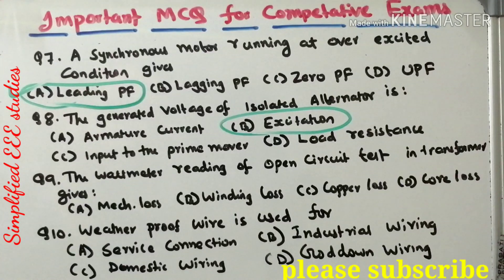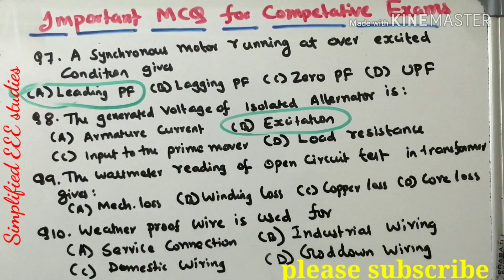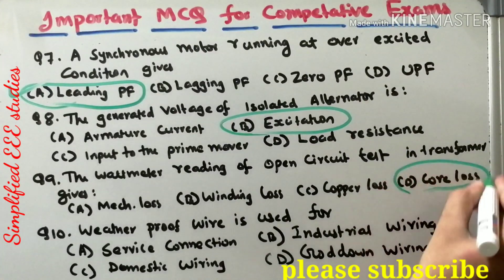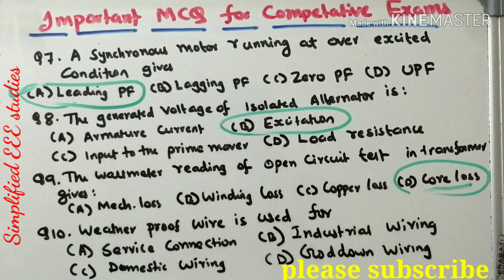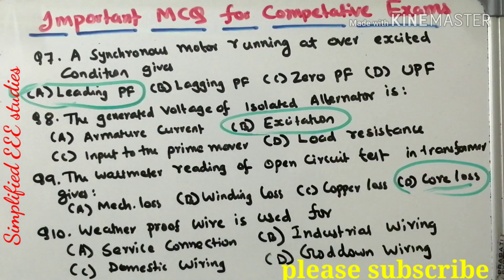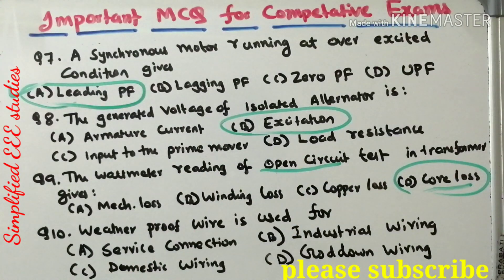Question 9: the wattmeter reading of an open circuit test in a transformer gives what? Open circuit test is mainly applied to the primary winding while the secondary winding is kept open. The main purpose of conducting the open circuit test is to evaluate the total core loss or iron loss occurring in the transformer. For the short circuit test, we can predetermine the copper loss. The right answer is option D: core loss.